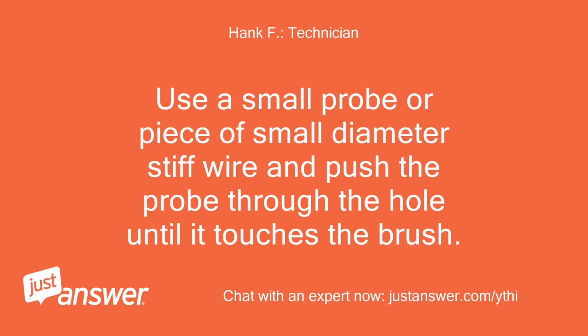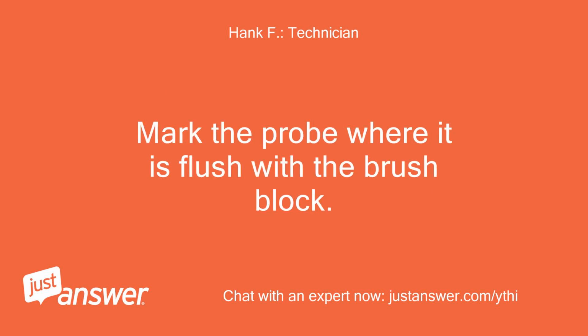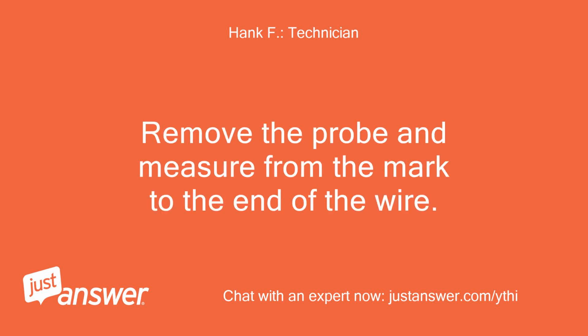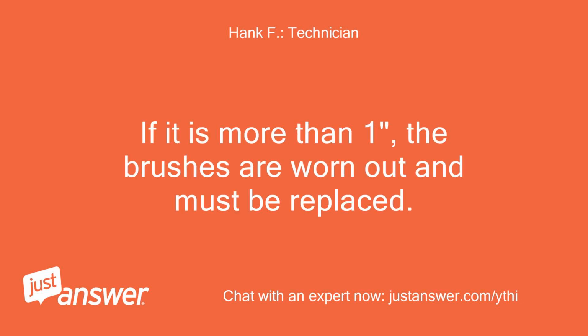Use a small probe or piece of small diameter stiff wire and push the probe through the hole until it touches the brush. Mark the probe where it is flush with the brush block. Remove the probe and measure from the mark to the end of the wire. If it is more than 1 inch, the brushes are worn out and must be replaced.